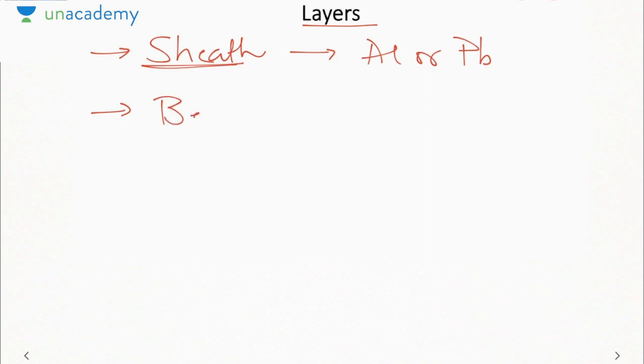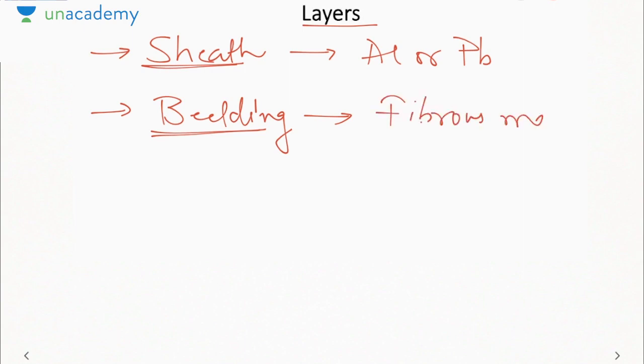Then outside that is bedding. The role of bedding is to protect the sheath layer from any corrosion, so that it does not react with any chemicals beneath the earth's surface. We have to place the bedding layer over the sheath layer. Here we can use any fibrous material like jute or cotton, something like that, which has fibers, and it should be cheap because its purpose is just to avoid corrosion on the metallic sheath. So it should be cheap only. It does not serve any other purpose.